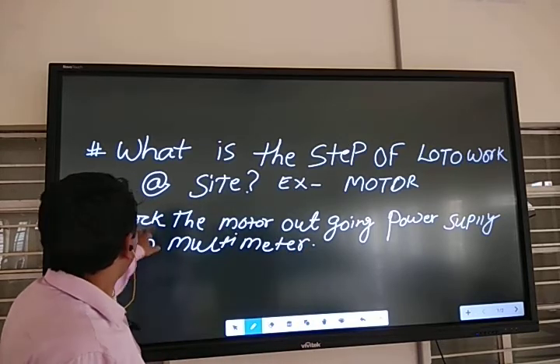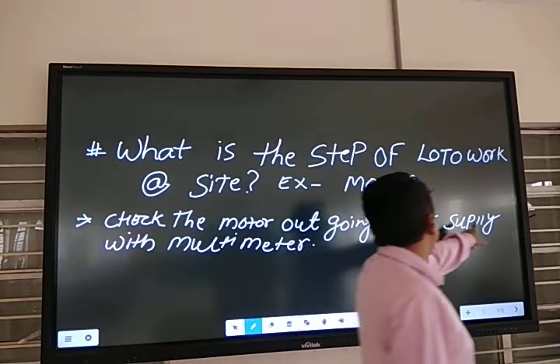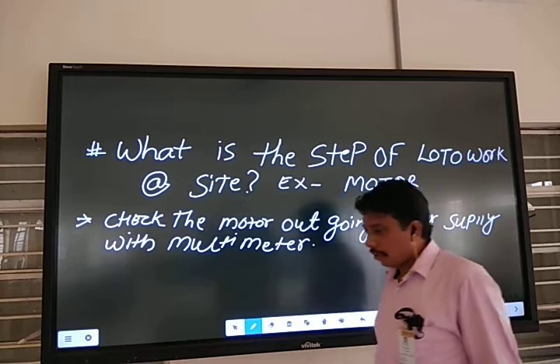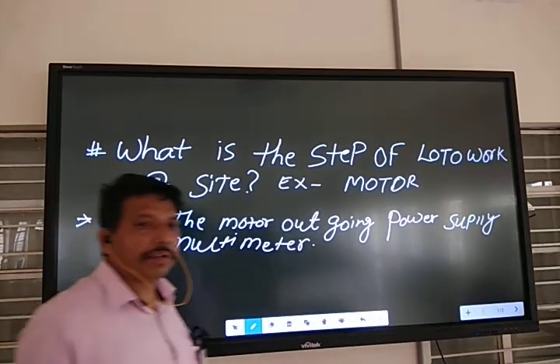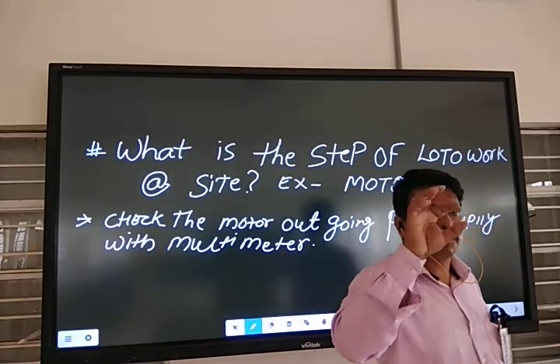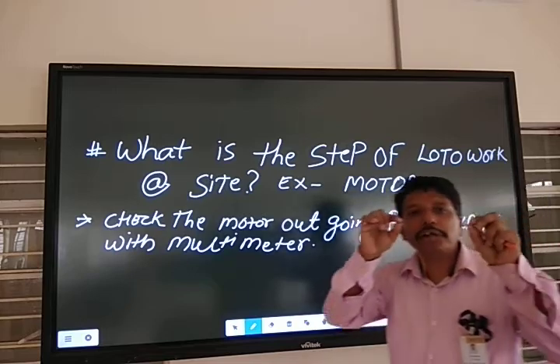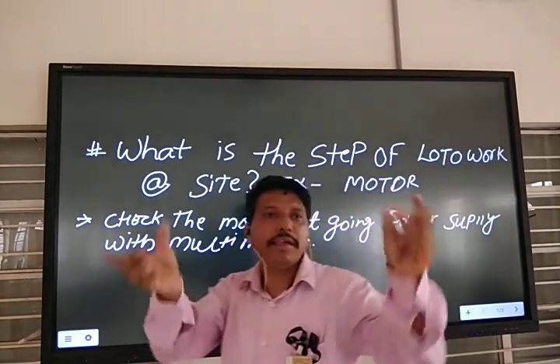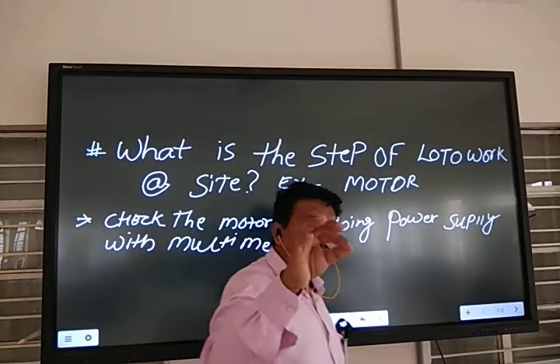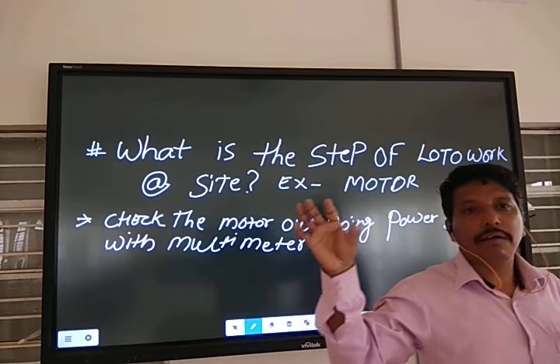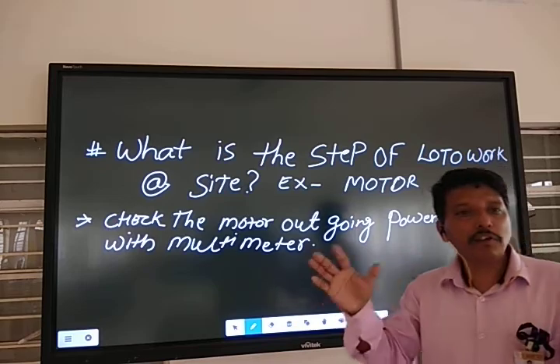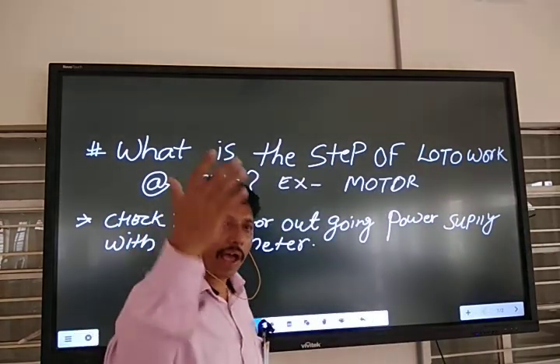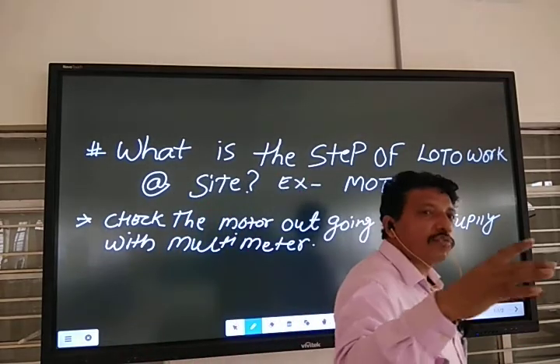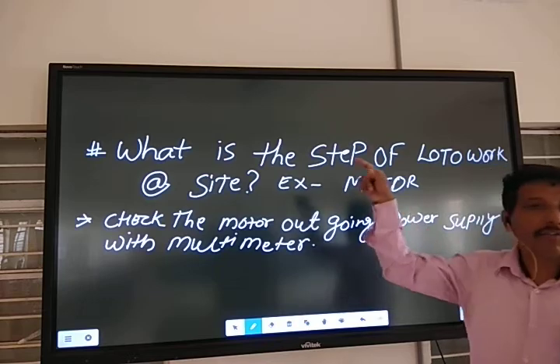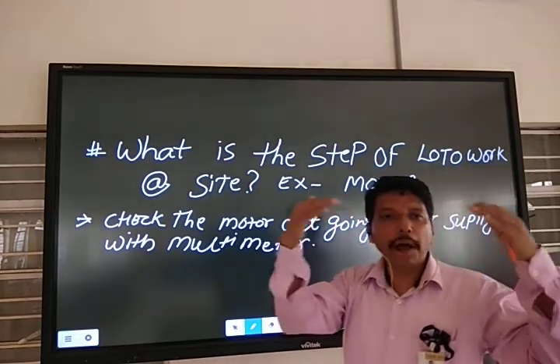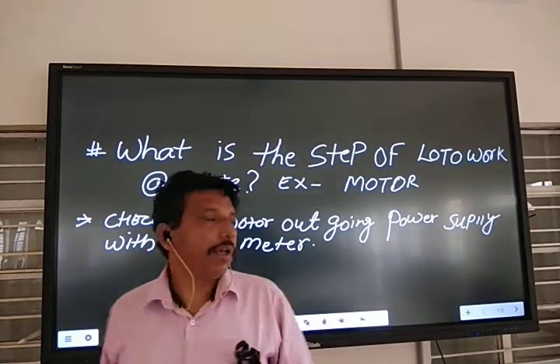Next, check the motor outgoing power supply with a multimeter. Sometimes the wrong drawing is given, or the drawing is not completed, so it's better to check with your multimeter whether there's power supply or not. If there is no supply, you can start the work. If there is current or voltage present, you cannot work on this motor, because during motor maintenance you must stop the power supply.